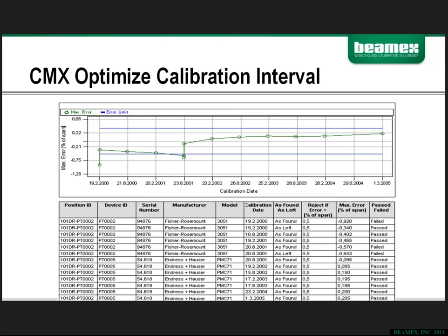So what we're hoping that you would be able to see through using this would be, if you were to extrapolate that out to look at the entire facility, how many calibrations can you eliminate over the course of the year just by doing a history trend analysis? Or how many underperforming instruments can you identify that are going to reduce the amount of time that it takes to service? Because as you've seen, once you do a calibration and it's out of tolerance, if you have to adjust the device, then you just invested more time in that one particular asset, which keeps you away from doing other maintenance activities. So in the big picture, it can save you a lot on both sides of the page, both in terms of underperforming and overperforming assets.